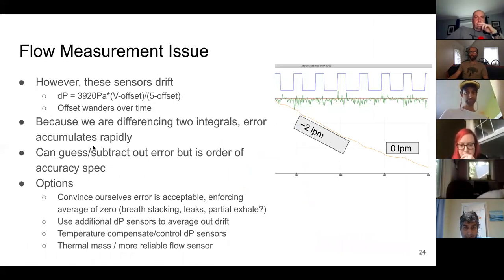The flow measurement channel has had some pretty long threads about this, but the main issue is the way the sensors work: there's an offset, and that offset is very temperature dependent. It's a strain gauge measuring pressure.